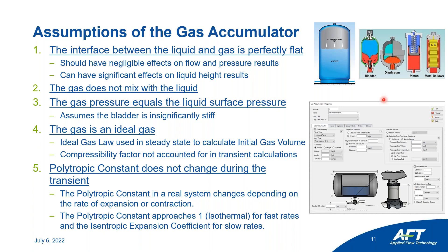The last thing I want to discuss are the assumptions the gas accumulator feature makes so that you can best model your gas accumulator and understand what's going on. The first assumption is that the interface between the liquid and the gas is perfectly flat. This should have negligible effects on flow and pressure results, however it can have significant effects on the graphed liquid height results. Secondly, the gas does not mix with the liquid — we assume the transient is fast enough that there's no gas mixing into the water and going down into your piping system, and that the gas stays separate from the liquid at all times.